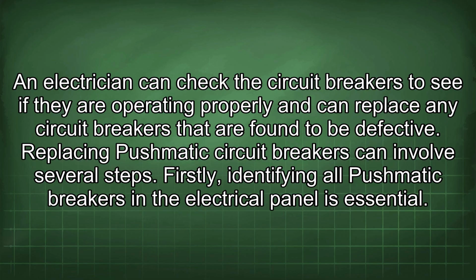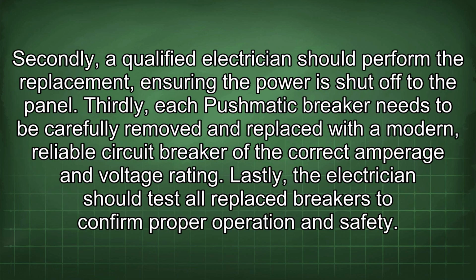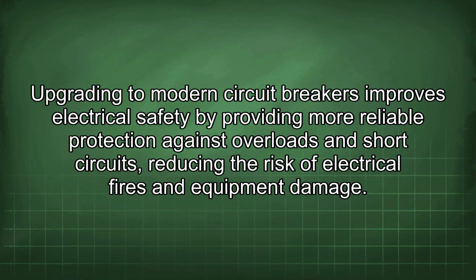Replacing Pushmatic circuit breakers can involve several steps. Firstly, identifying all Pushmatic breakers in the electrical panel is essential. Secondly, a qualified electrician should perform the replacement, ensuring the power is shut off to the panel. Thirdly, each Pushmatic breaker needs to be carefully removed and replaced with a modern, reliable circuit breaker of the correct amperage and voltage rating. Lastly, the electrician should test all replaced breakers to confirm proper operation and safety. Upgrading to modern circuit breakers improves electrical safety by providing more reliable protection against overloads and short circuits, reducing the risk of electrical fires and equipment damage.